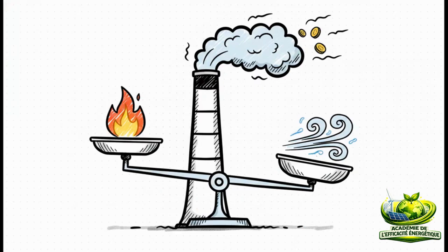Now, obviously, fuel needs oxygen to burn. But the holy grail here is what we call a stoichiometric balance. That's the absolutely perfect, ideal fuel-to-air ratio needed for complete combustion. Now, the big mistake operators make? Tipping way past that balance. In the real world, yes, you do need a little bit of excess air to be safe. But when you crank it too high, you're just heating up completely useless nitrogen and water vapor, and then sending all that expensive heat straight out the exhaust.